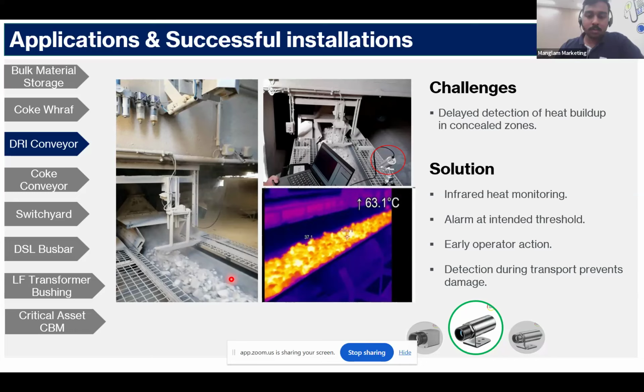I will just add from our experience: you have to identify which are the critical areas in your conveyor system where there's a likelihood of hotspot generation. Each camera typically covers about 2 meters of the conveyor length, depending on the distance. People typically put it at the entry point or exit point from one process into the other, so they can monitor the temperature of the product as it gets transferred into the next zone.